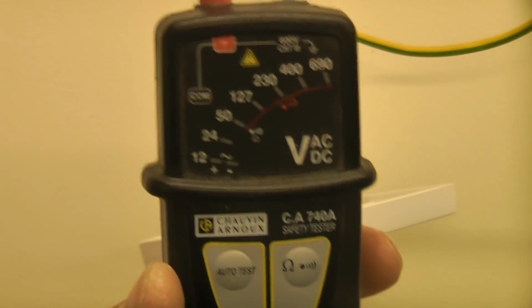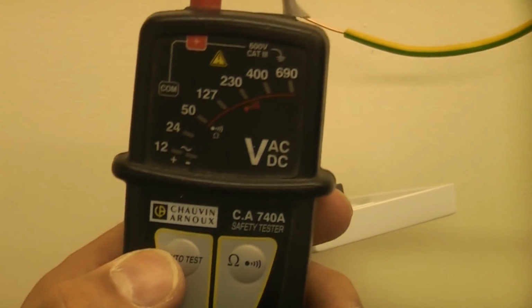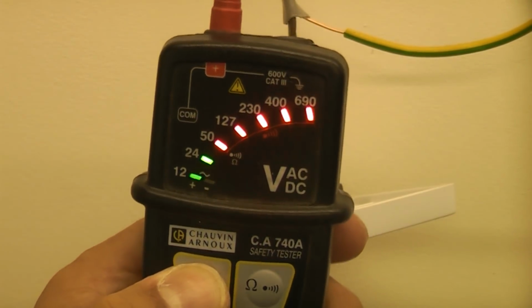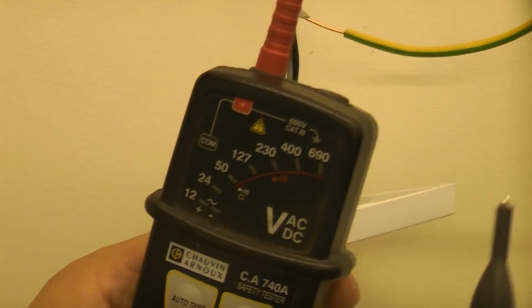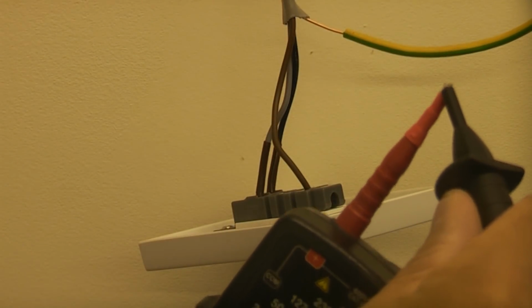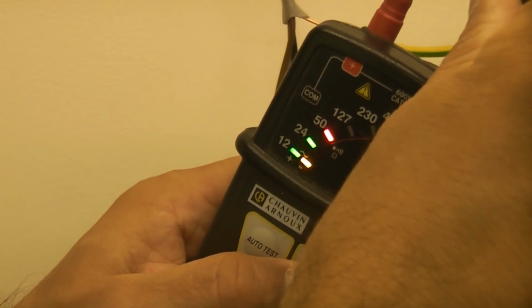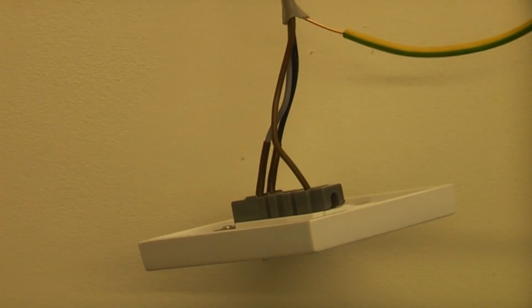We now need to test the machine is still working. So I'm going to press the auto test button, and then I'm going to test the leads are still in good condition by touching them together and pressing the continuity test. So we can now safely say that that is isolated safely.